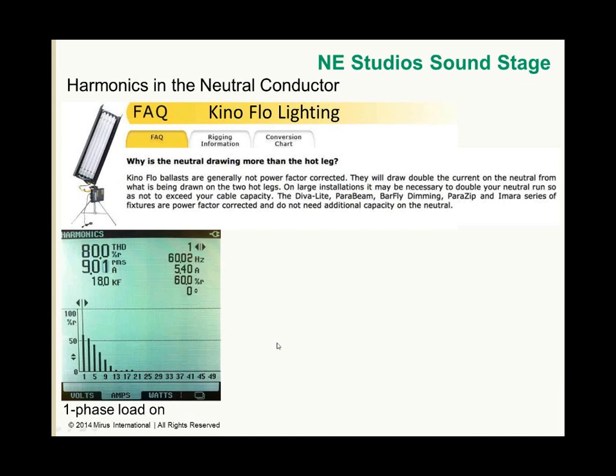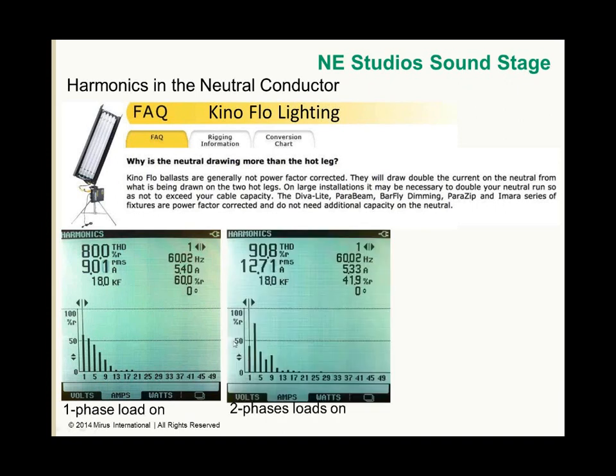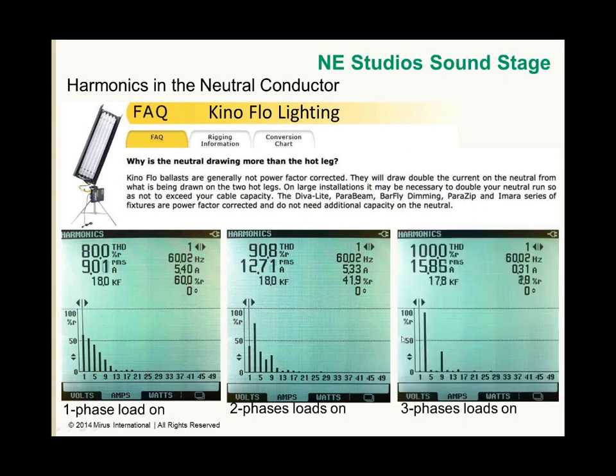When load is placed on the second phase, the fundamental and the 5th and 7th harmonics begin to cancel, but the triplens, the 3rd and 9th, increase. With load on all 3 phases, the fundamental, 5th and 7th harmonics are almost non-existent, but the 3rd and 9th are very high. And overall RMS current is greater than the phase currents. So here we've got an RMS current of almost 16 amps, and the phase currents are 9 amps each.